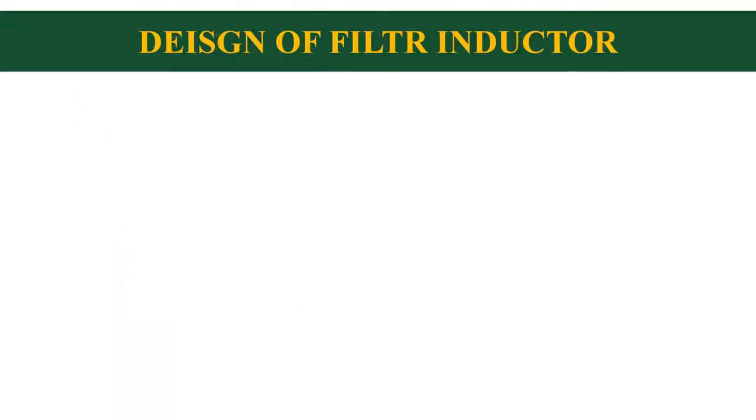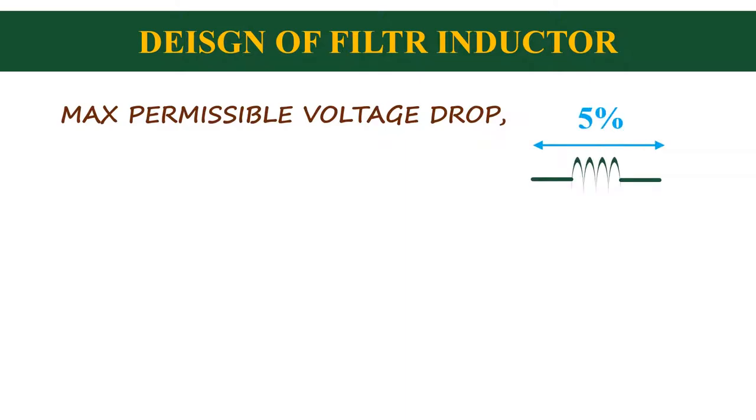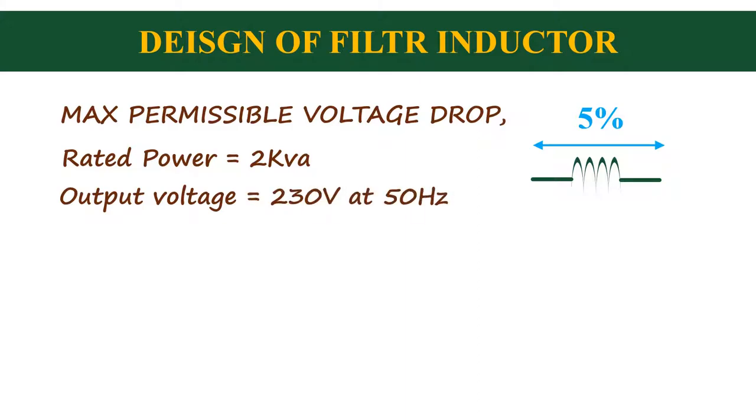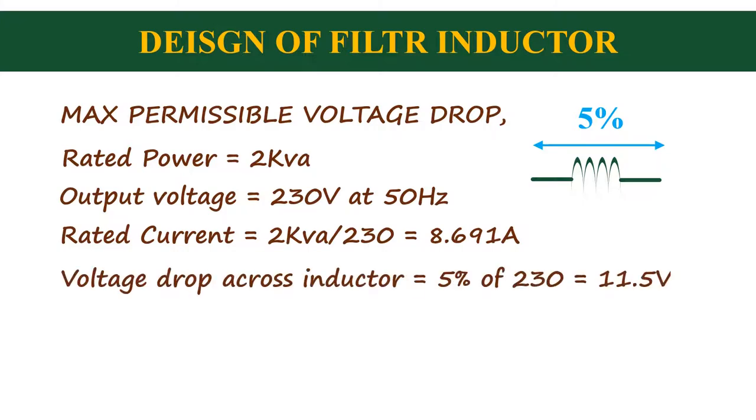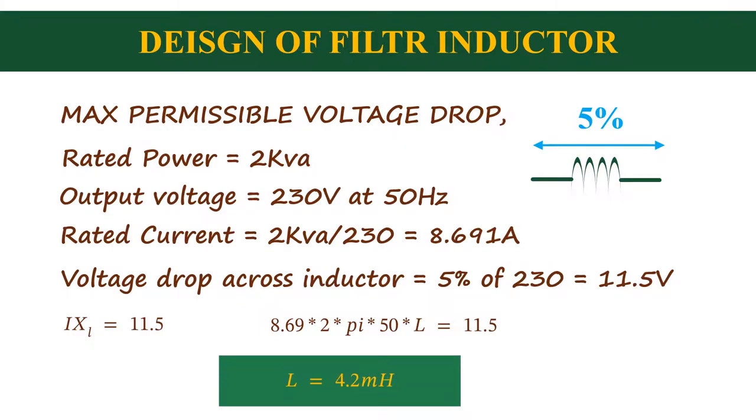Now I will tell you how to design the value of the inductor. The design of the inductor is based on the maximum permissible voltage drop across it. For this design, I am considering a maximum voltage drop of 5 percentage of the grid voltage. Now let me give the specification of Statcom. Maximum power is 2 kVA. The output voltage is 230 volt at 50 hertz. Rated current is 2 kVA divided by 230, that is 8.69 amps. Now the voltage drop across the inductor is equal to 5 percent of 230, that is 11.5 volt. As we know, equation for the voltage drop across the inductor is I into XL. Equate this with 11.5. Substitute all the values, and then we will get inductance as 4.2 mH.